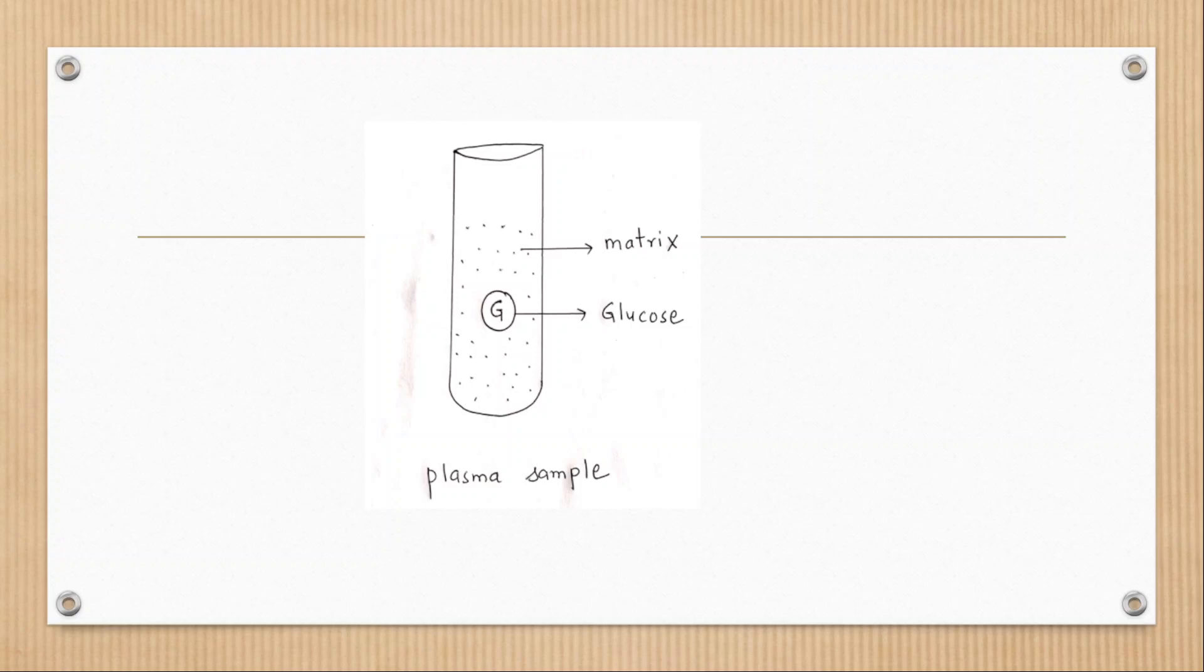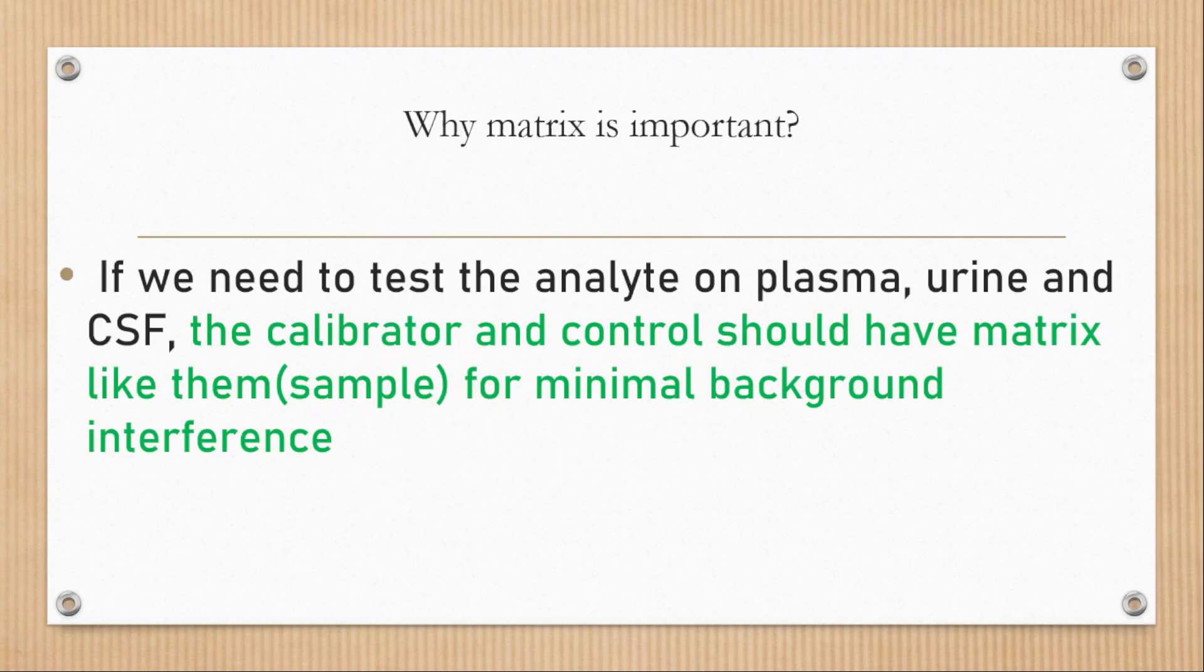Now, why matrix is important? If we need to test the analyte on plasma, urine, CSF, and other body fluid, the calibrator and control should have matrix like sample for minimal background interference from test method and machine.